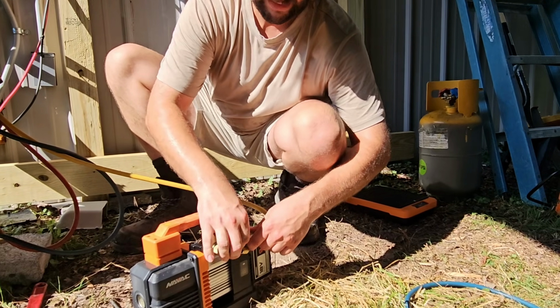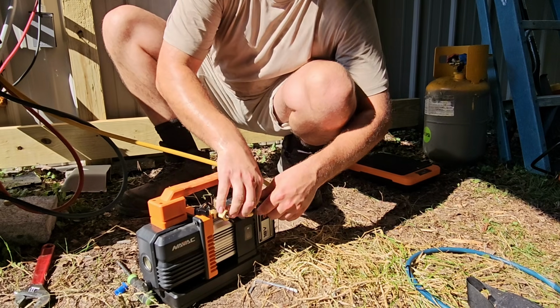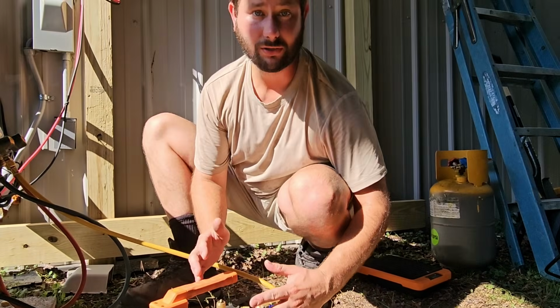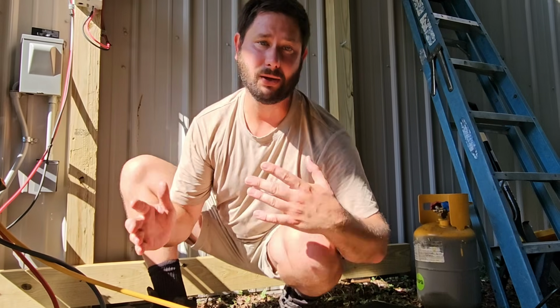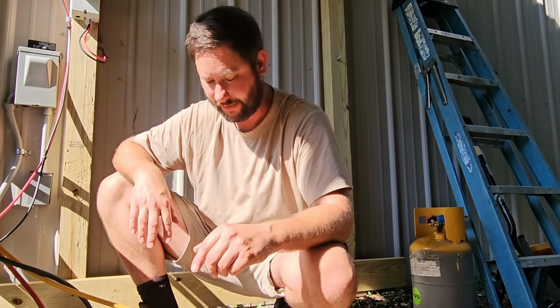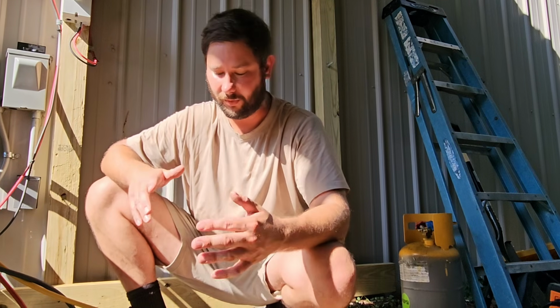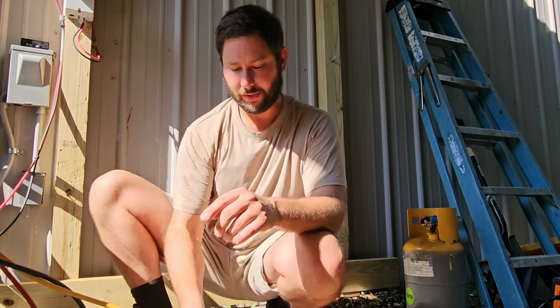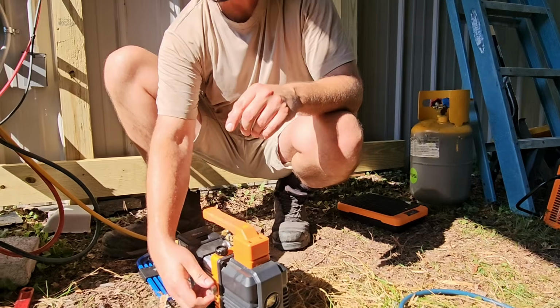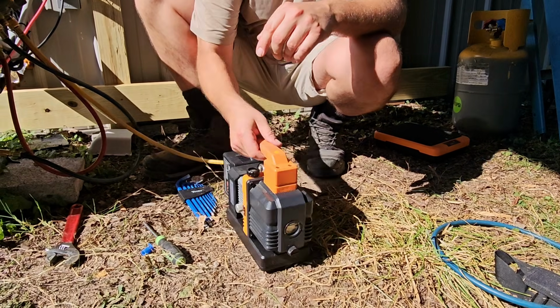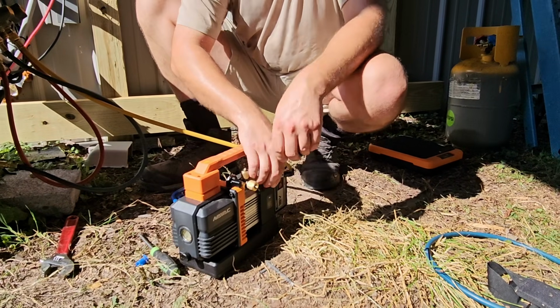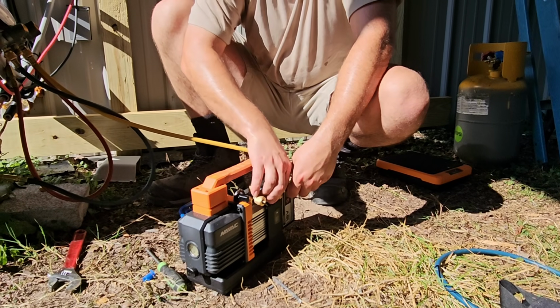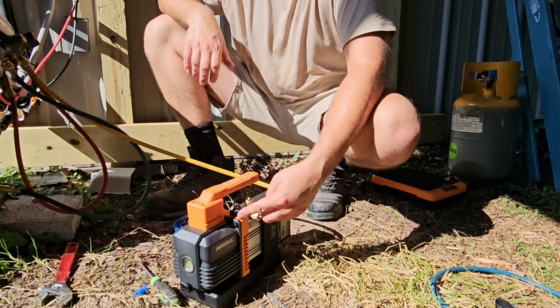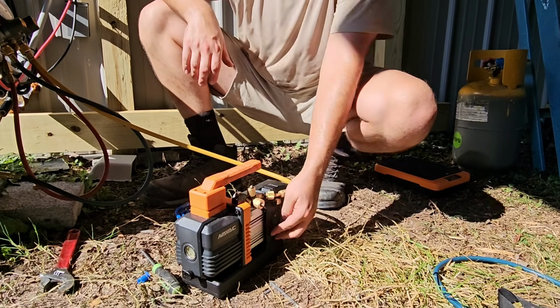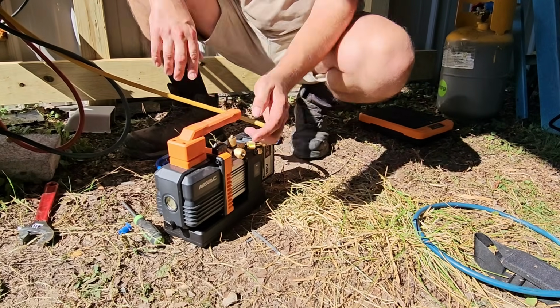Be careful when you're connecting your gauges and your hoses to your pump. If there's a lot of pressure, it's going to blow the oil out of the pump, and you don't need that. Plus, it'll make a mess. This is NAVAC's DC vacuum pump, so it is compatible with A2L refrigerants. To pull a good vacuum, we're going to open the ballast right here, make sure our pump is screwed on and our hose is screwed on, and then open up our valve. Open up the valve, and then push the button to turn on the pump.